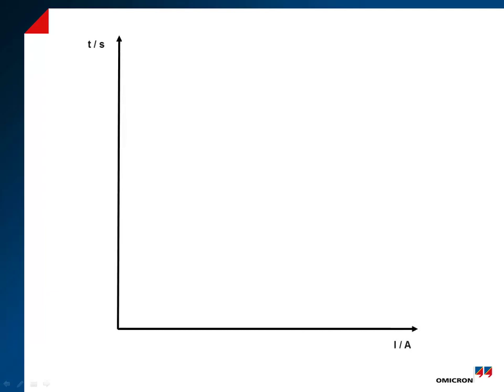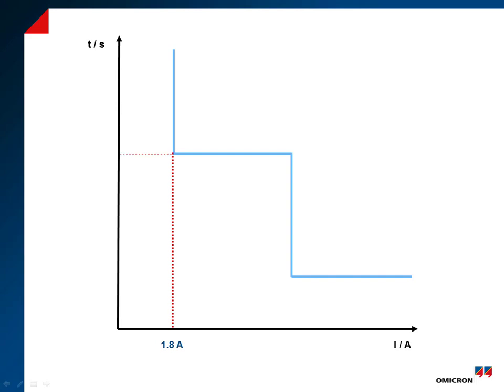As shown in this figure, the first element trips at 1.8 amps with a delay time of 500 milliseconds. The second element trips at 6 amps with a delay time of 100 milliseconds.